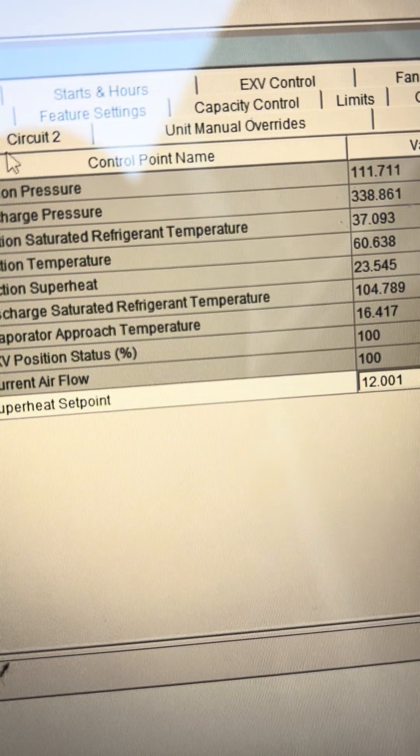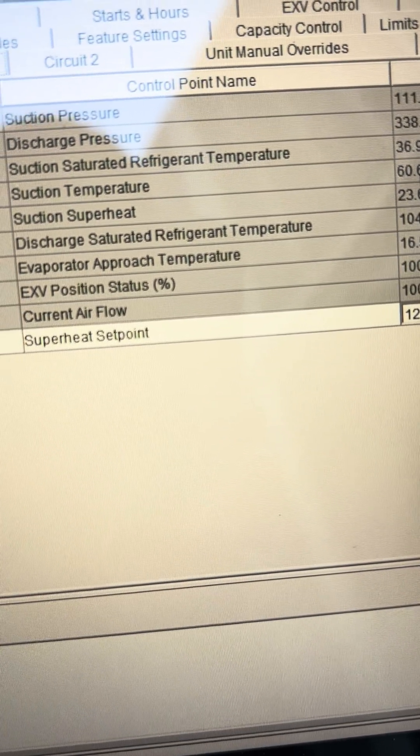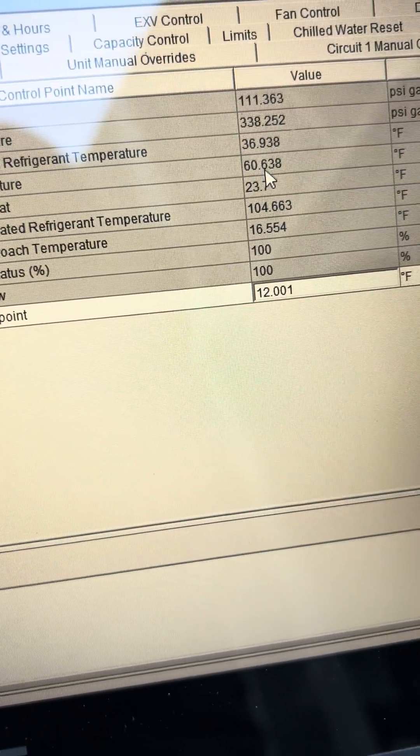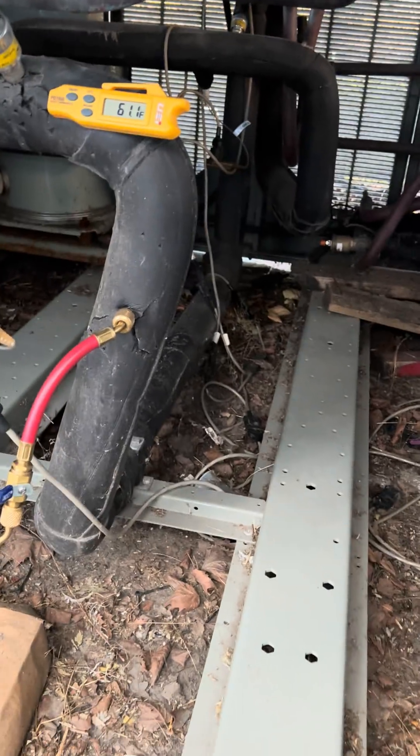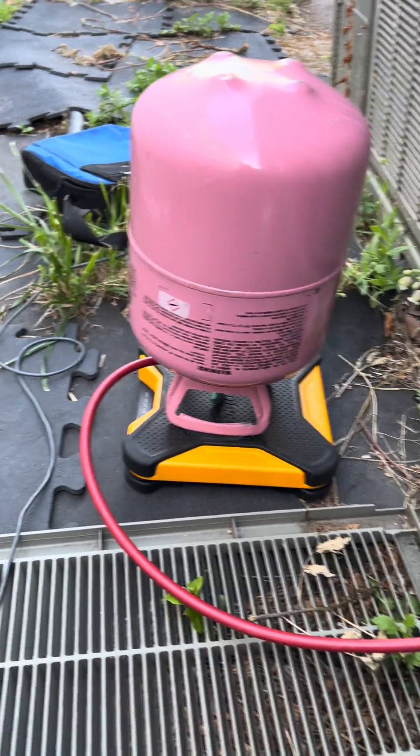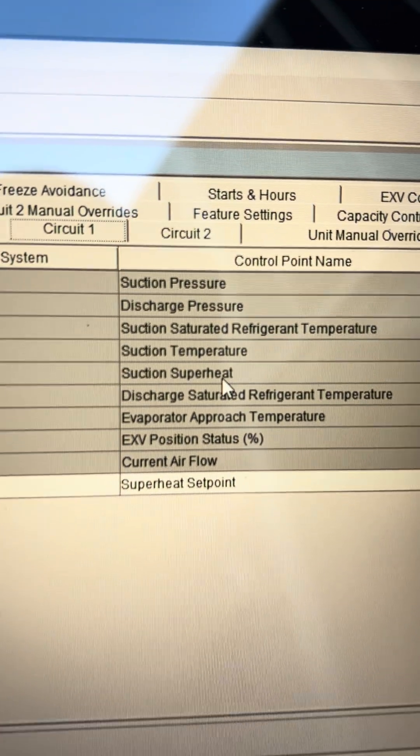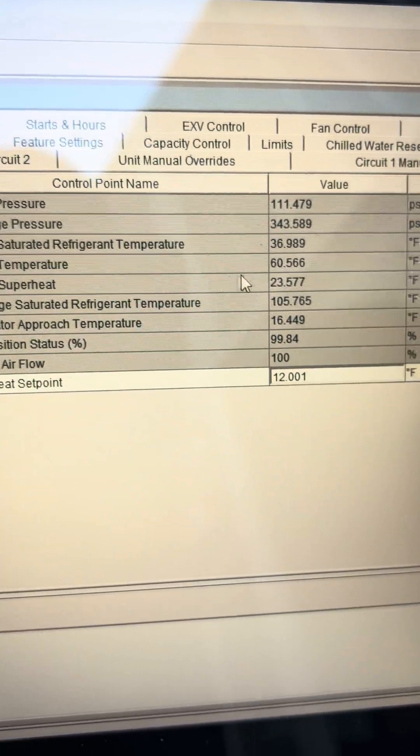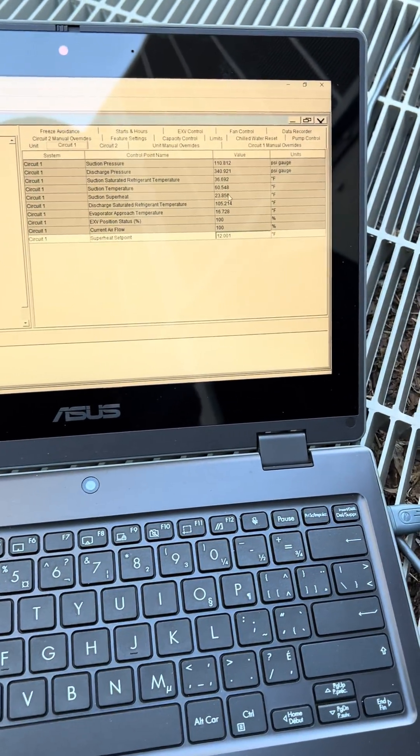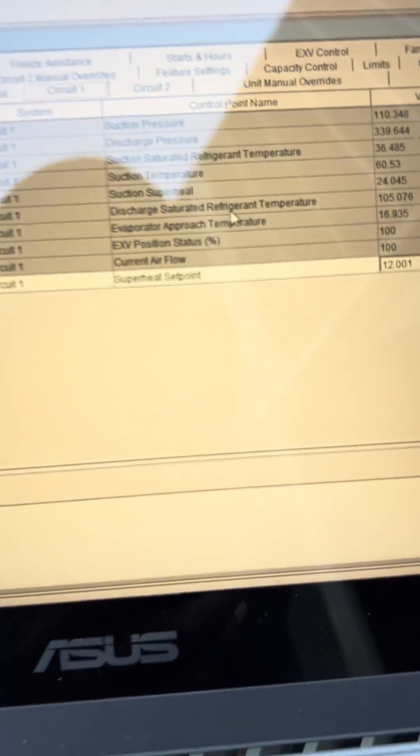Circuit number one suction line temperature is 60 degrees which is rather high. I got my thermometer on the plate to confirm that. I got my scale set up and my refrigerant and my hoses, they already know where I'm going with this. Then we have our superheat, superheat.